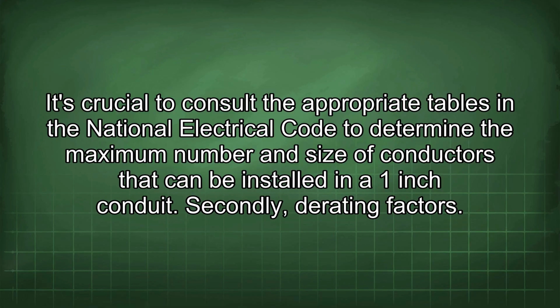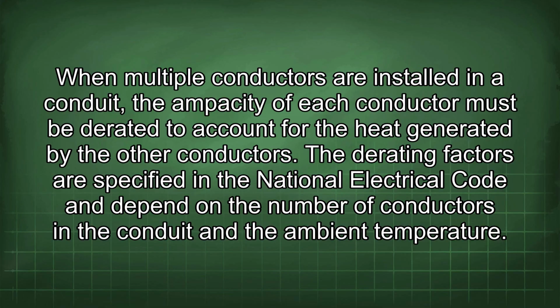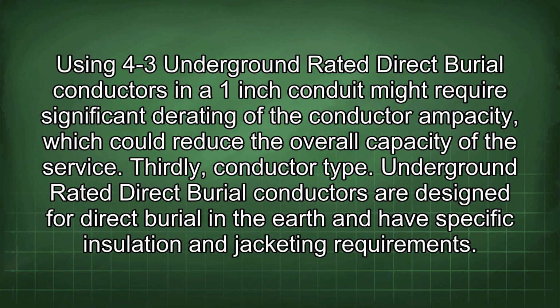Secondly, derating factors. When multiple conductors are installed in a conduit, the ampacity of each conductor must be derated to account for the heat generated by the other conductors. The derating factors are specified in the National Electrical Code and depend on the number of conductors in the conduit and the ambient temperature. Using 4-3 underground rated direct burial conductors in a 1-inch conduit might require significant derating of the conductor ampacity, which could reduce the overall capacity of the service.